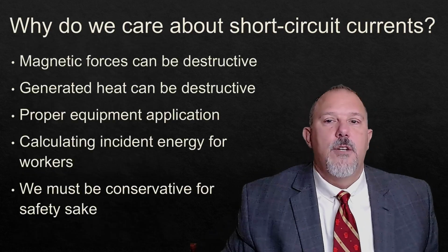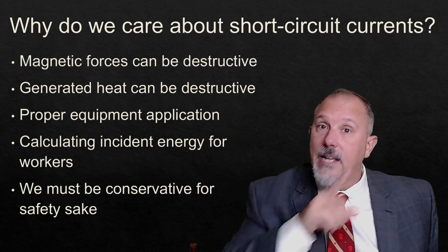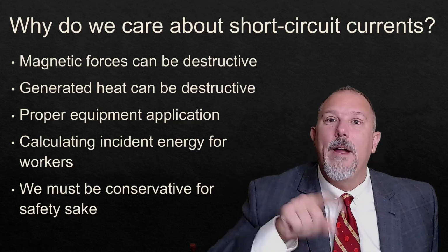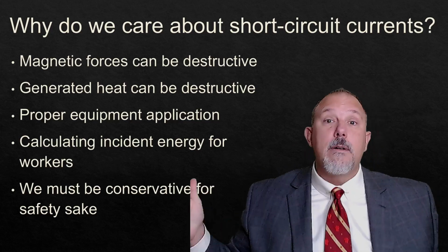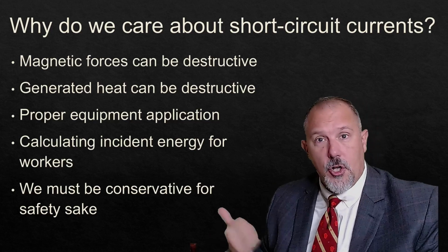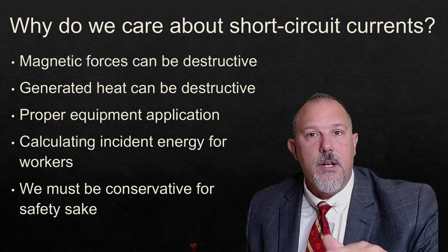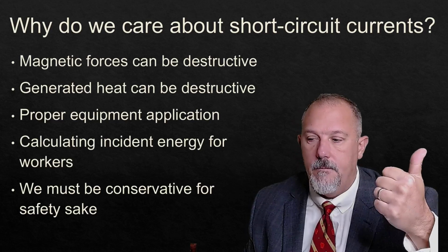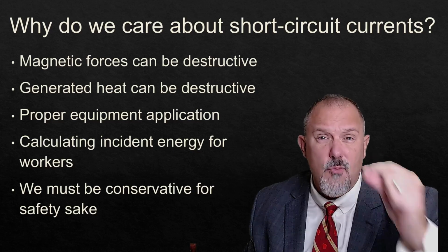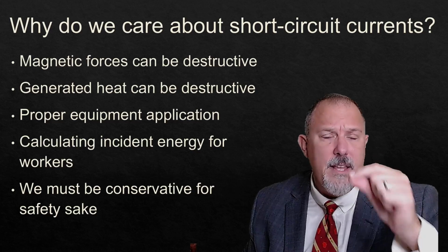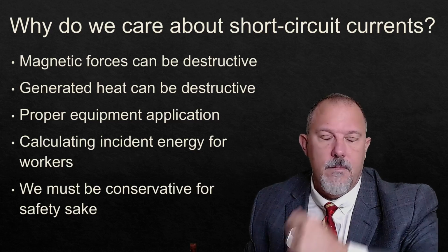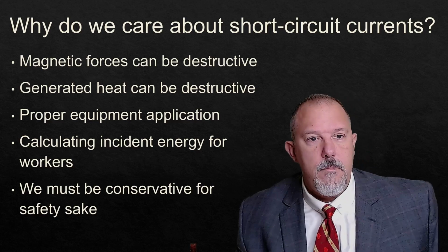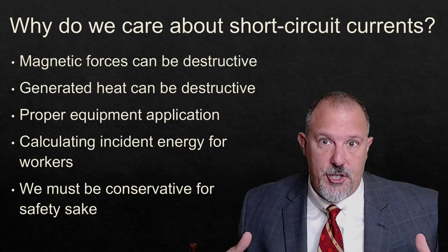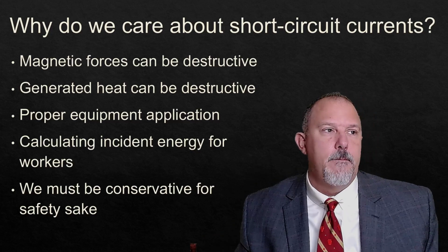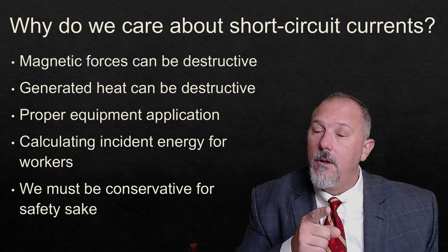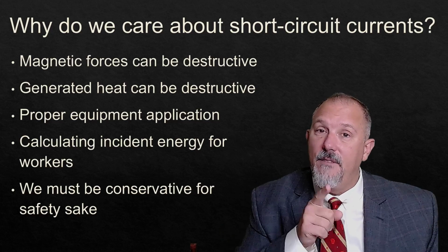why do we care about short circuit currents? Well, short circuit currents that go outside of the path, they went outside of the path for a reason. Not just because they took a detour and it was lunchtime and they said, hey, we're going to go park it over here. No, they went outside of the path because either a wrench got dropped, or something happened to disrupt that current and give it a path to some other location. Something bad, probably. You have magnetic forces. You have arc flash, incident energy. You have heat. You have an explosion. You have what we call an unintended rapid disassembly in the field.